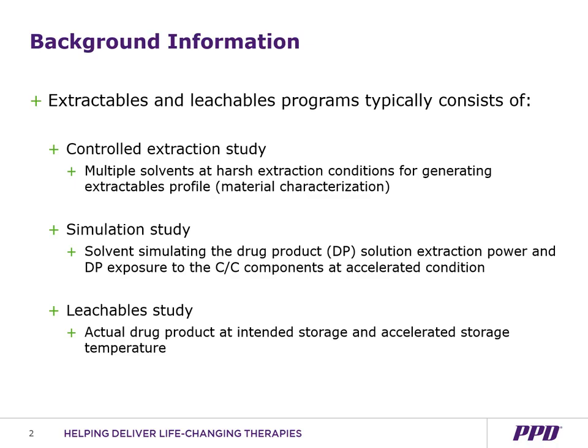Let me start with some background information. Extractable and leachable studies typically consist of three types of studies. One of them being a controlled extraction study, where you are exposing the container closure components to multiple solvents at harsh conditions to generate an extractables profile.